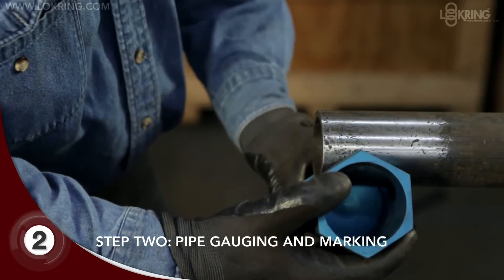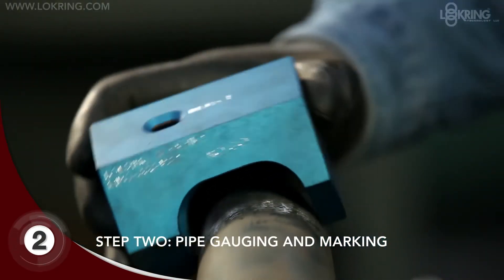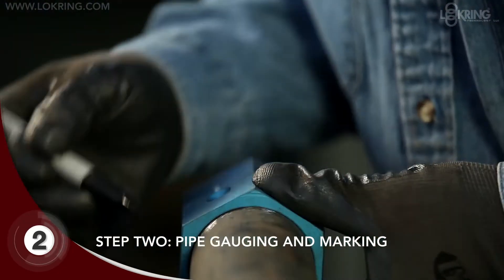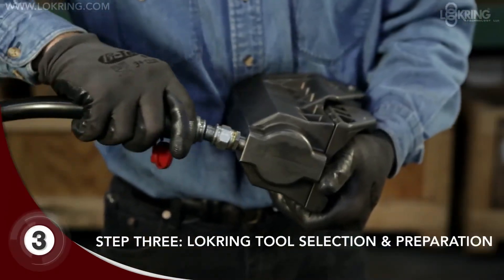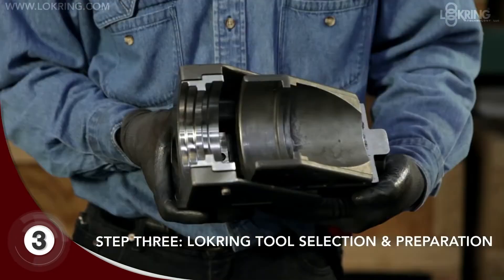Using the caliper or half moon side of the Lokring multi-purpose gauge, verify that the pipe's outside diameter is not undersized and then mark the ends of the pipe with an installation and inspection mark. With that step completed, you can select and assemble the required Lokring tool. Inspect and cycle the tool to ensure proper function.